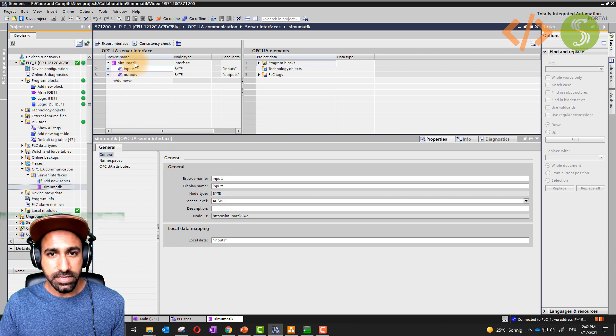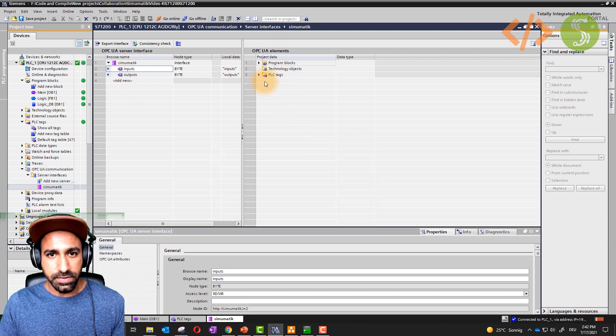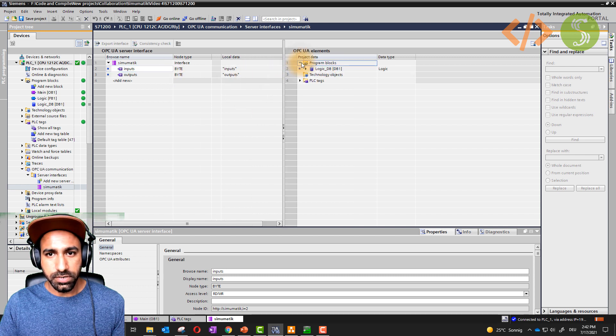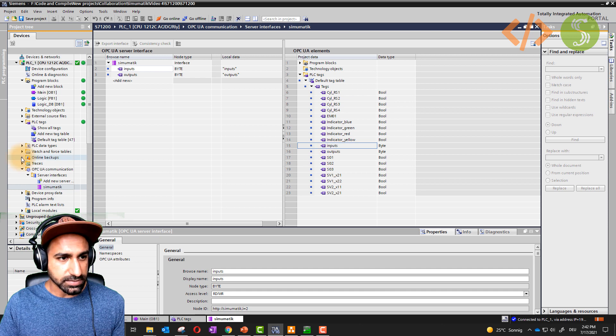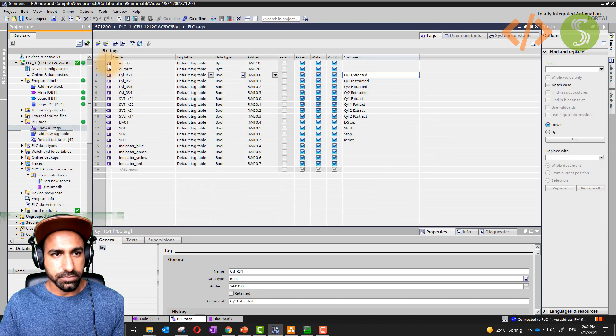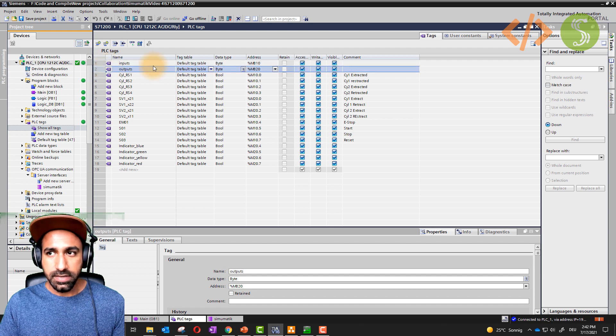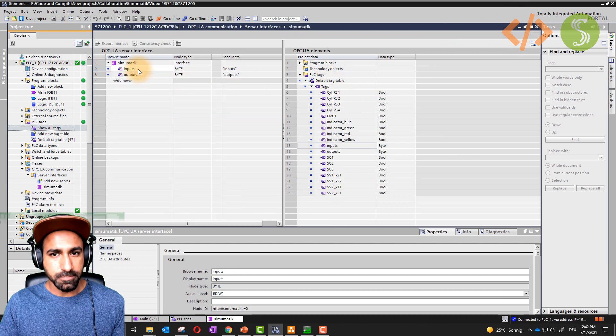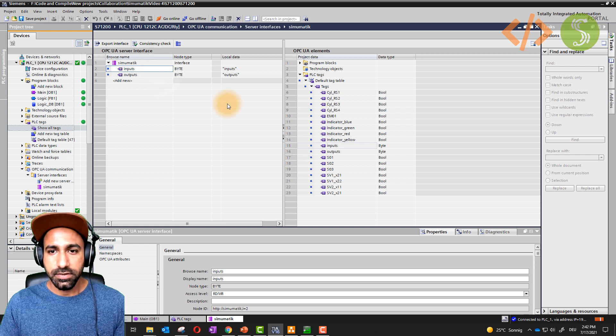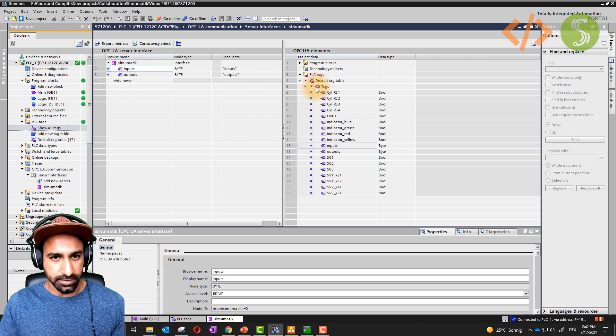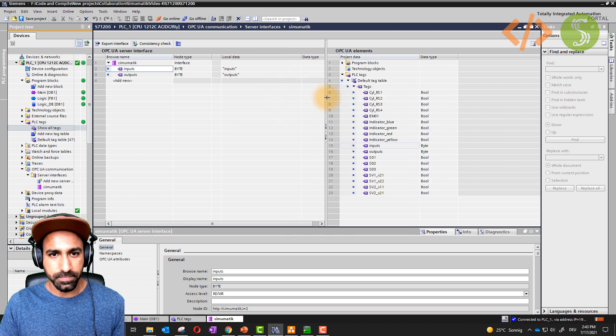Once you click Add New Interface and rename it, you'll see a window where you define the tags. You can go to PLC Tags, where I have defined input and output. If you go to PLC Tags → Show All Tags, you'll see my input and output tags. I just took these two tags and dragged them into my OPC UA interface — drag and drop — and then they are linked to your OPC UA interface. You can then download the logic to the PLC.